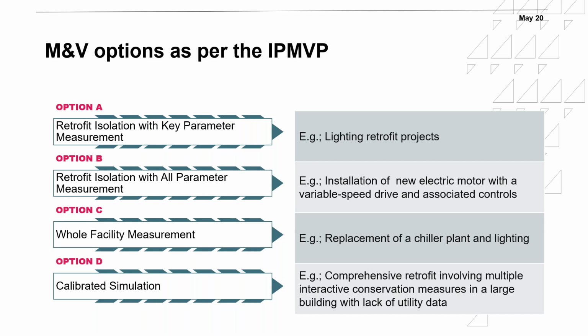The problem here is that the adjustments are a bit scary, to be honest, because you need to be very careful. You need to capture all data that will change the consumption within that building. Because again, you're not looking at the chiller on its own, you're looking at the whole building. And then you need to make sure that you know exactly what's happening within the building during the baseline. And then in the reporting period, you need to go and check. You had, let's say, 20 DX units, they've added 5 more. You need to go there and do an adjustment for the baseline, saying that if those 5 DX units were there in 2018, what would have been the consumption? So it's a bit tricky from the adjustments. If, let's say, not a lot will change in the building, option C becomes very good.